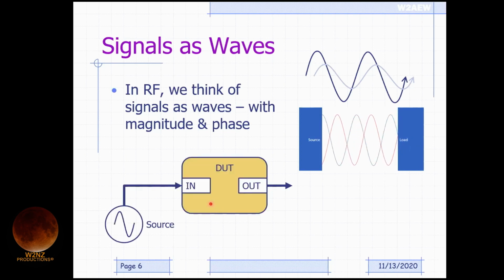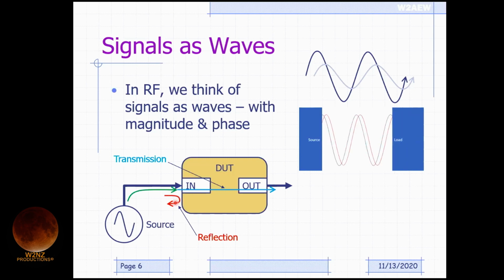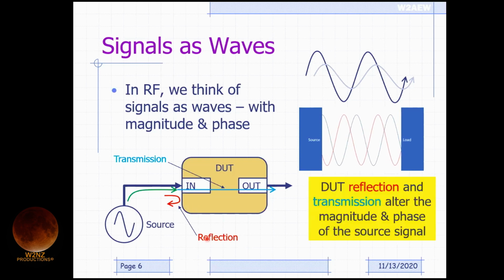So again, when we start thinking about waves and a VNA, one of the things we're going to be concerned with is a signal being applied from the source, and then some of that signal, ideally, if we have a two-port device, is going to go through that device. It could be an amplifier, a filter, a mixer, whatever it might be. Those are what are called the transmission properties of the DUT. And also, if we have an impedance mismatch at this point here, we may have some signal reflected off of that input port to the device. Those we call, obviously, the reflection properties. So the DUT reflection and transmission will alter both the magnitude and phase of the signal that's being applied, and that's what we look at on a VNA.